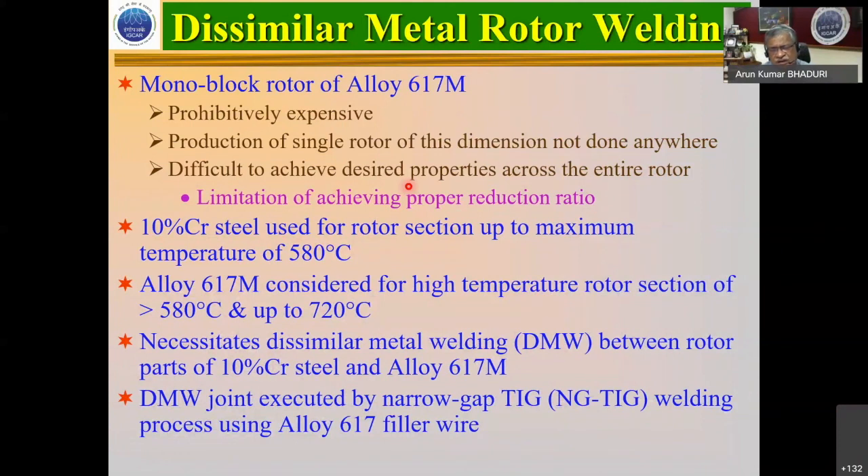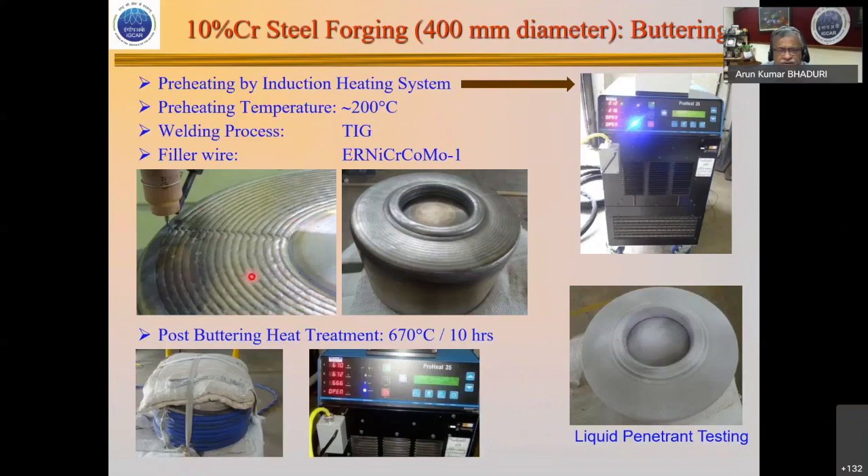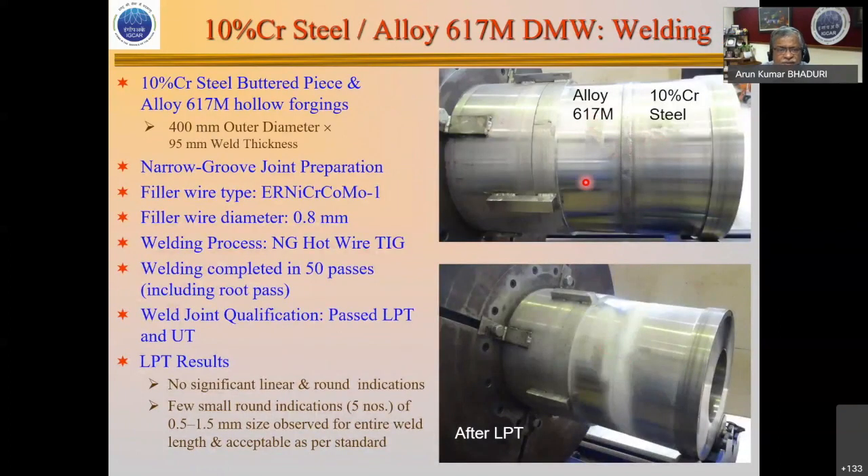The major challenge was the dissimilar rotor weld: the 9-chrome steel rotor works up to 580°C, but we are going up to 720°C, requiring a dissimilar weld joint. We used the narrow-gap welding machine available at IGCAR with a 400 mm torch. We performed buttering first with a 617-composition filler tailor-made for this work, followed by post-buttering heat treatment, and then completed the weld. For the 400 mm rotor this has been demonstrated; the 800 mm rotor has just come off the machine. There is a pocket in the current weld that needs to be addressed — in a closed weld configuration we must ensure proper purging at the root level.